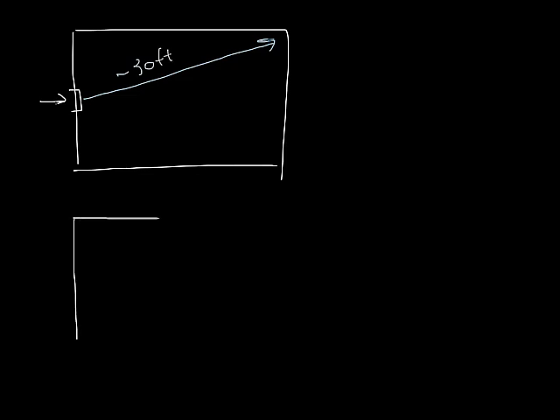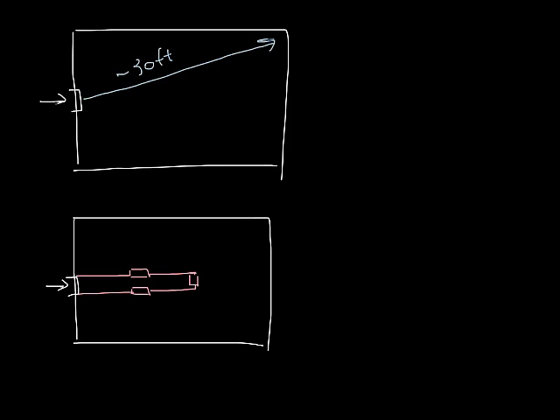What you often see are air highways in the plenum. Air highways are basically duct work run in the plenum that have dampers to control the airflow to the plenum. It might look something like this. So from the damper to the farthest diffuser is now only 30 feet.